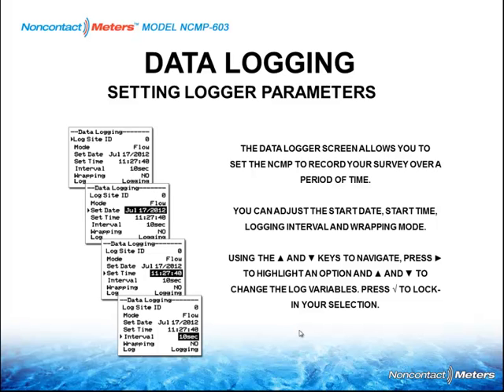Now the sample interval is programmable from 10 seconds and more. Remember, we said we have 300,000 data points, but you do get a ton of data if you're taking samples at 10-second intervals. Generically speaking, if you're just doing a flow study on a normal application, most people tend to take a snapshot once a minute, which will give you 1,440 data points in a day. The software accommodates this, and it will accommodate the 10 seconds there. But if you export it to Excel, you get 30,000 data points, and Excel begins to get pretty muddy. So sometimes too much information is too much information.